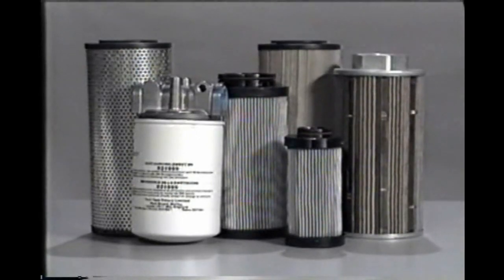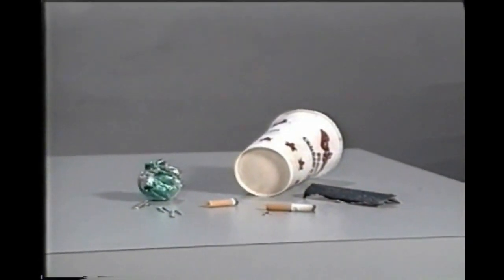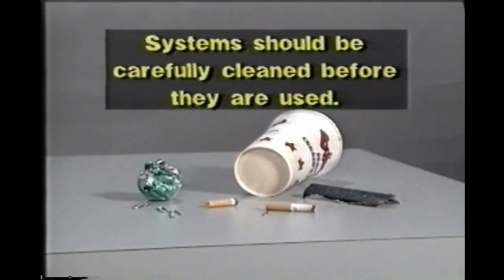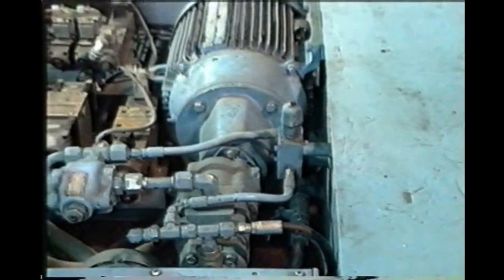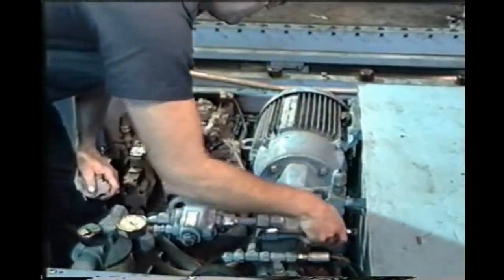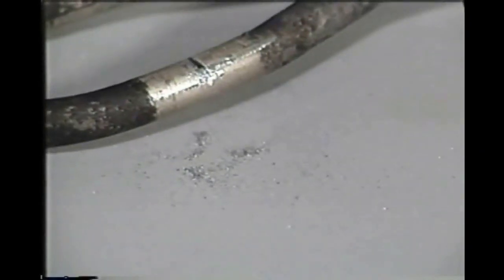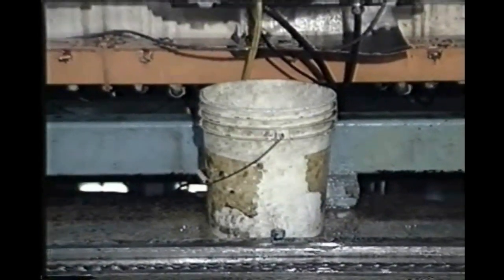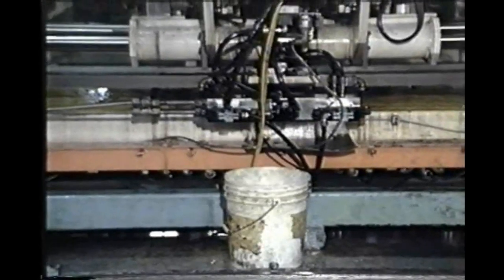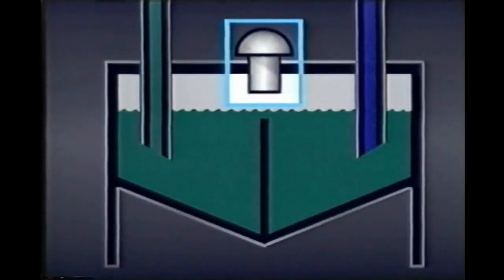Filters remove dirt from a hydraulic fluid, but there's a lot you can do to keep dirt out of the system in the first place. Paper cups, cigarette butts, metal chips, emery paper, rust, paint—all of these have been found in the reservoirs of new systems, so all systems should be carefully cleaned out before they are used for the first time. Dirt will likely get in when the system is first installed, and more may get in when repairs that open up the system are made. If parts of the system are disassembled, they may be worked on at a dirty workbench, then wiped off with an old rag before being reinstalled. When new parts are added to the system, slivers of metal may also wind up in the reservoir. If hydraulic fluid is caught in a bucket until repairs can be made, the oil may be dumped back into the reservoir. Dirt will almost certainly be in the bucket, and it will contaminate the entire system.